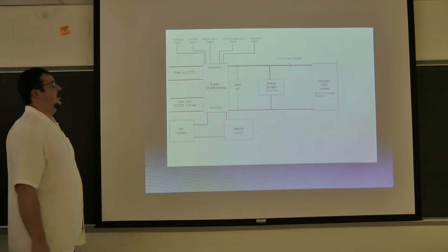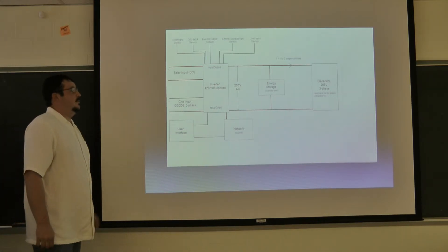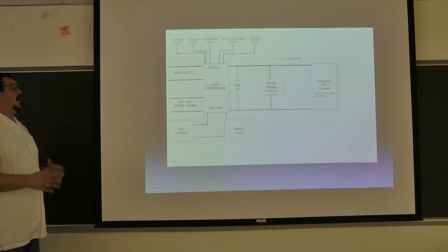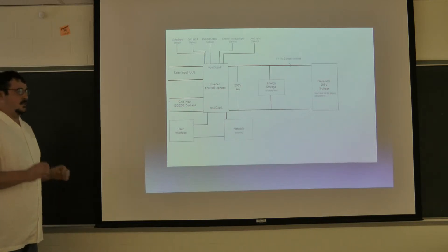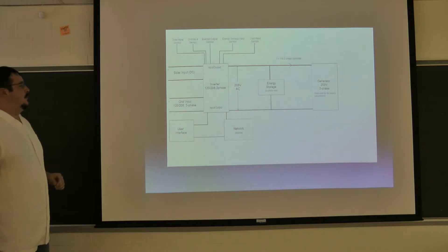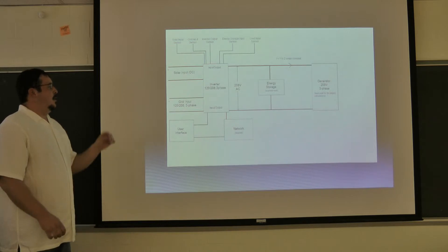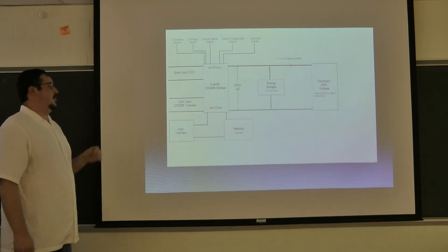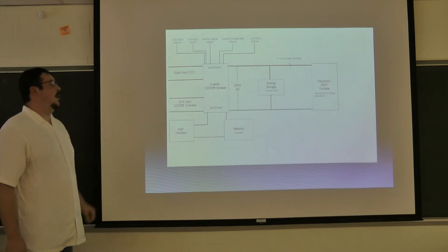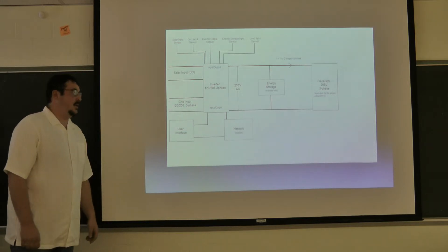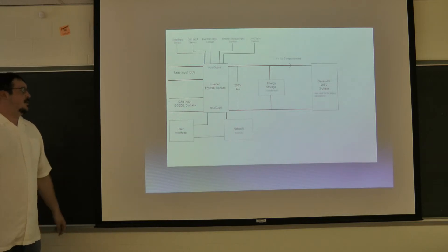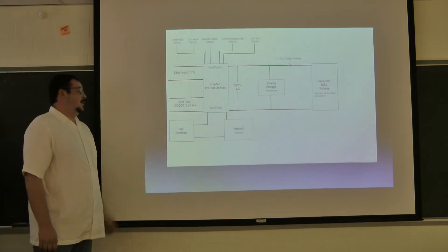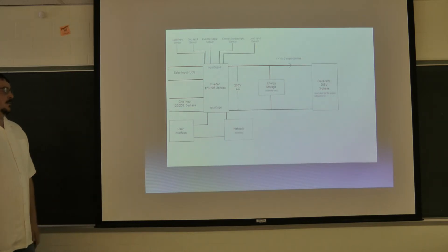This is a brief diagram of what we are going to have — the solar input and grid input going into the inverter, with a secondary load as a dump for the AC supply. We want to supply a 1.5 kilowatt max load at all times. We still need to add our battery backup, with an automatic transfer switch that senses when solar can no longer support the system and switches to battery. We also need to synchronize the grid input so the grid takes over the load in case of any emergency. User interfaces will be networked over time.